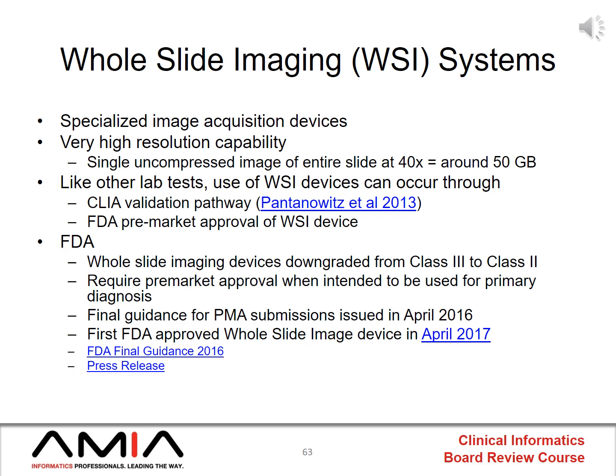The use of whole slide imaging devices can occur clinically through a specified validation pathway under CLIA, but it also can occur if you use an FDA-approved whole slide imaging device. Now, the FDA recently downgraded whole slide imaging devices from Class 3 to Class 2, which would enable them to go through the 510K pathway. Final guidances for whole slide imaging devices are provided as references on this slide.